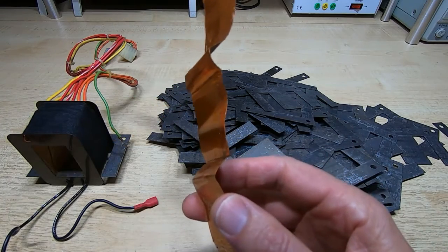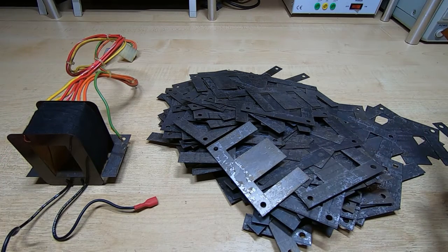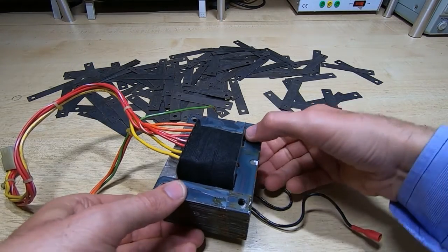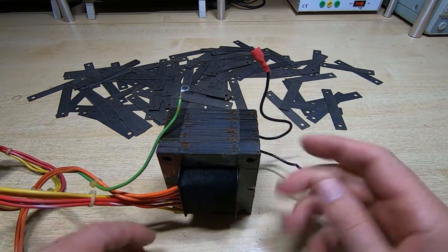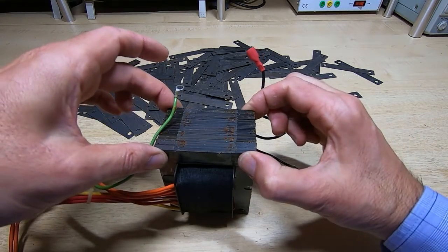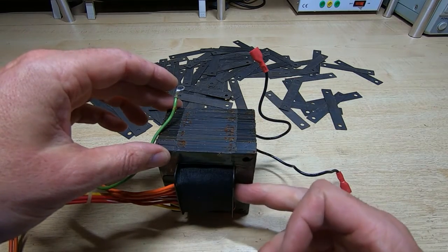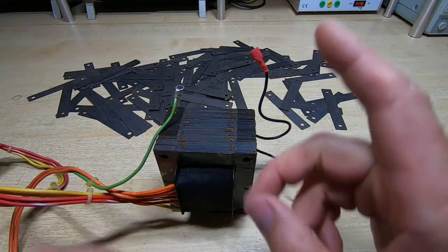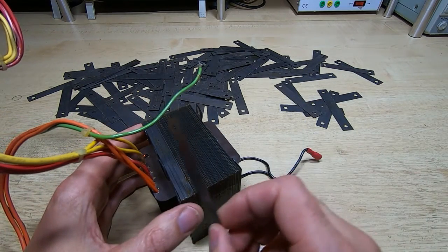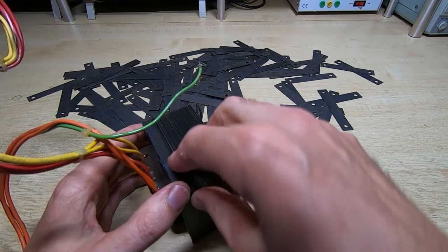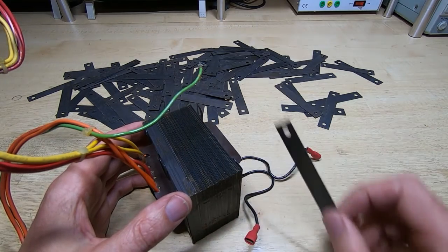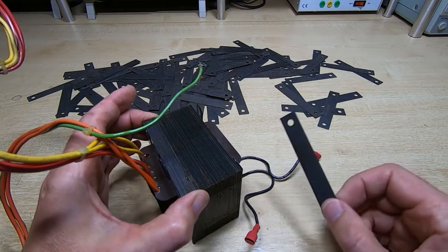That's all the laminations in place. As ever, the last few were quite a snug fit in the core. If you remember there was a gap at the end of the core when I took this apart and this will compress slightly when we put the clamping screws in. Now we've got the E pieces in, the next thing to put in place are the I pieces. It's just really a case of working our way along and slotting each of these in place and pushing them down.